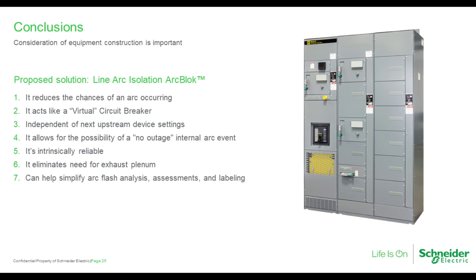So that's been a lot of innovative information to digest. So in conclusion, I want to take some time to go over just some of the important bullets that you've heard today, just to reiterate. One being the ArcBlok solution reduces the chance of an arc occurring. Two, it acts like a virtual circuit breaker. Three, independent next upstream device settings. Four, it allows for the possibility of a no outage internal arcing event, which we did state, you, Tim, and Erhan both touched on.